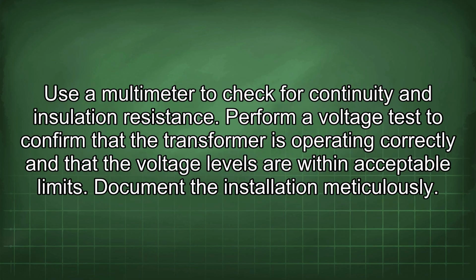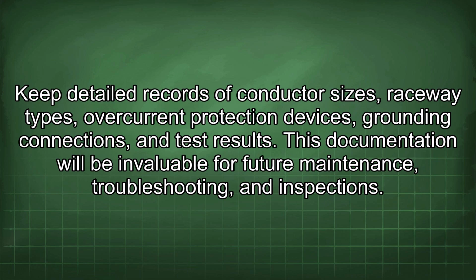Use a multimeter to check for continuity and insulation resistance. Perform a voltage test to confirm that the transformer is operating correctly and that the voltage levels are within acceptable limits. Document the installation meticulously. Keep detailed records of conductor sizes, raceway types, overcurrent protection devices, grounding connections, and test results. This documentation will be invaluable for future maintenance, troubleshooting, and inspections.